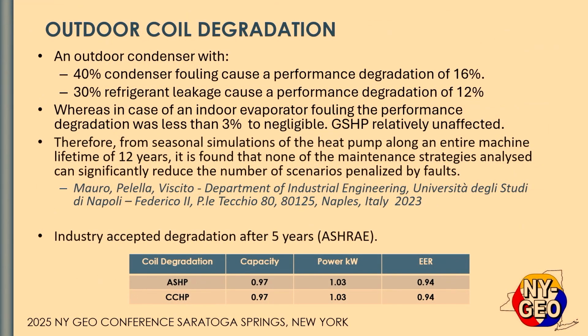And so I did throw in a little slide here, because if you do a Google search and look at what we've used in some of our software packages over the years from ASHRAE and whatnot, you find out that a 40% condenser fouling can degrade performance by 16%. There's typical refrigerant leaking, so you're going to have another 12% with that. So there are a lot of issues with an outdoor condensing unit.